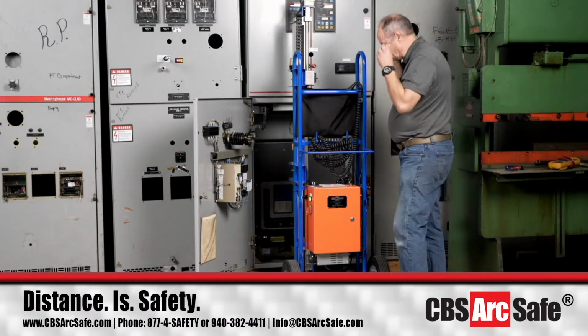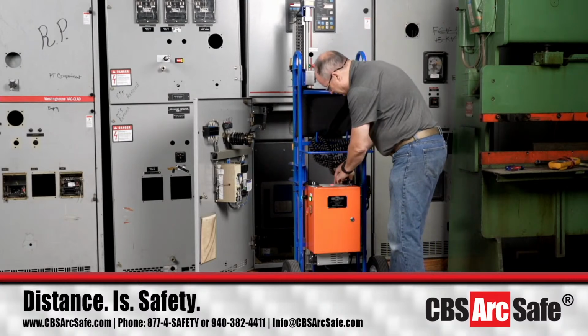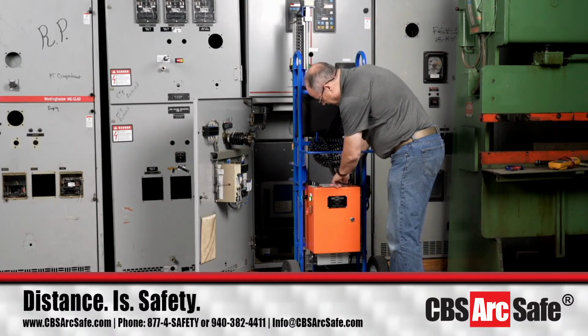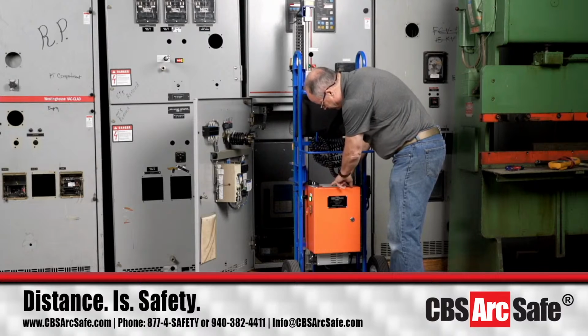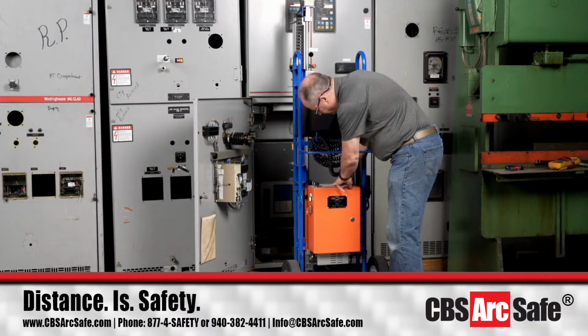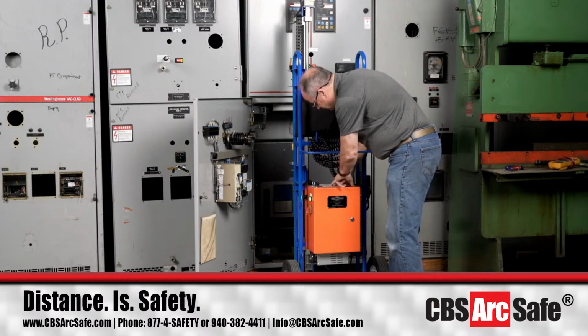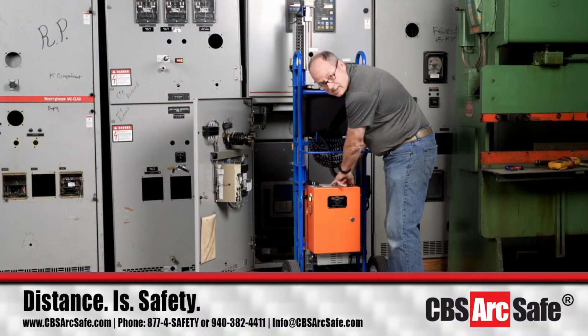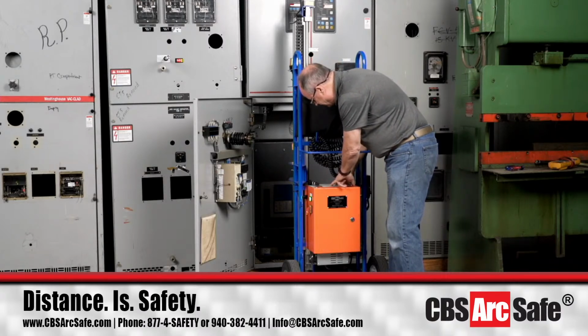So to start out with, the first thing I'm going to do for this breaker is put the numbers down to 0 for install and remove. That way we're going to let the breaker tell us how much force it takes to bring the breaker out.